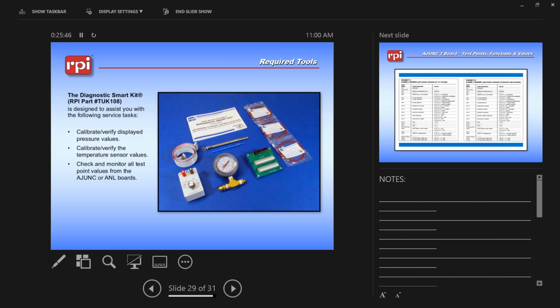Of course, inside the calibration kit, which we have listed here, this is our part number TUK108. On the right-hand side, you're going to have various different connectors that will allow you to connect to the AJUNC 3 board, the AJUNC 2 board, or the ANL T2 boards. Left of that on the bottom is going to be your test point board. Next over is your pressure gauge. And the last one on the end is the test box, which is going to simulate temperatures for your temp sensor. Up from that is the ribbon cable that's going to connect your test point board to your AJUNC board. And then of course there's a trim pot adjustment tool, a max register thermometer for checking the interior temperature, and then a booklet which is going to give you calibration information, how to do it, and also test points, which I will show you in just a moment.